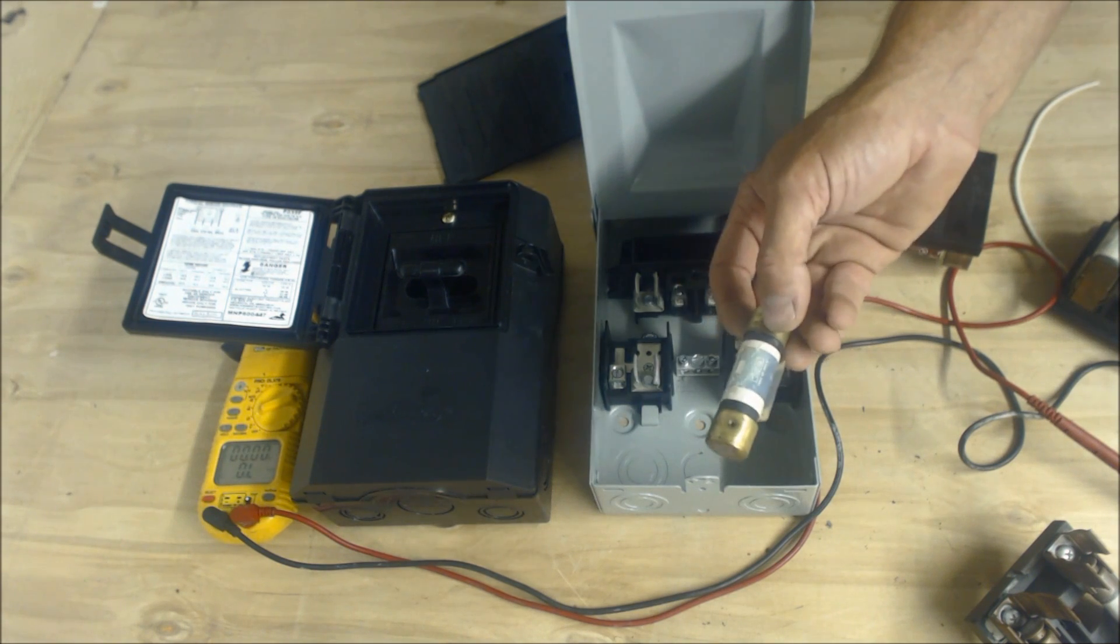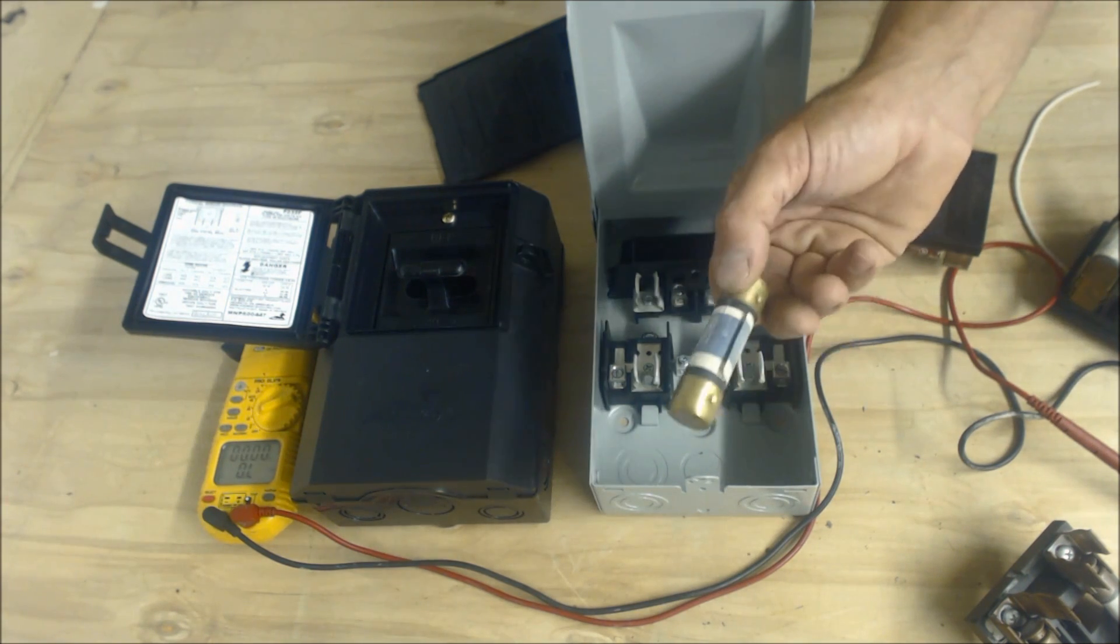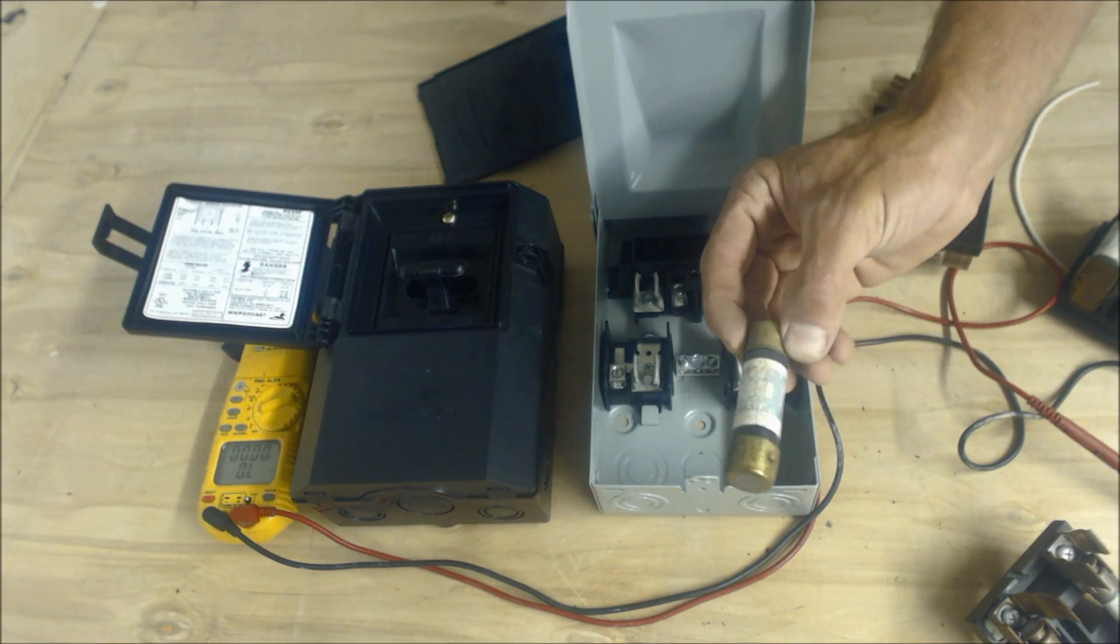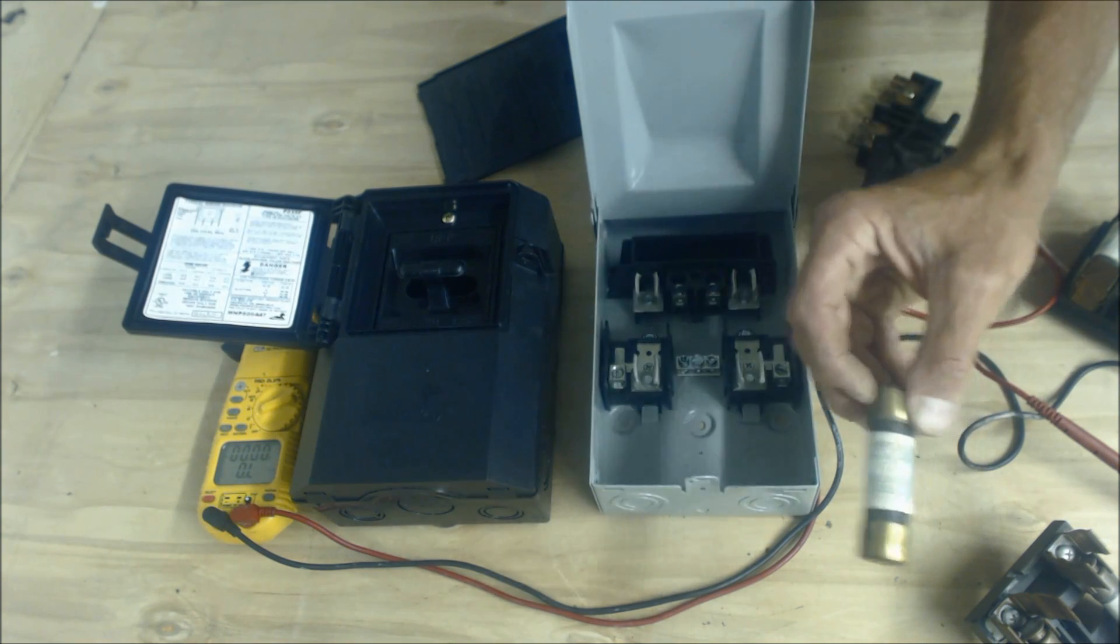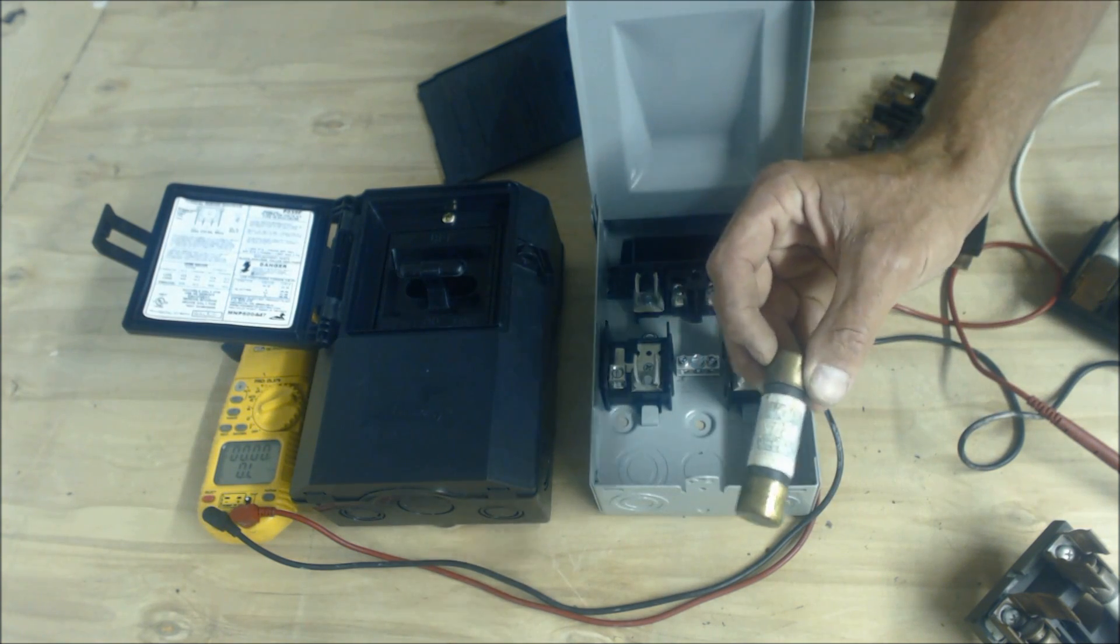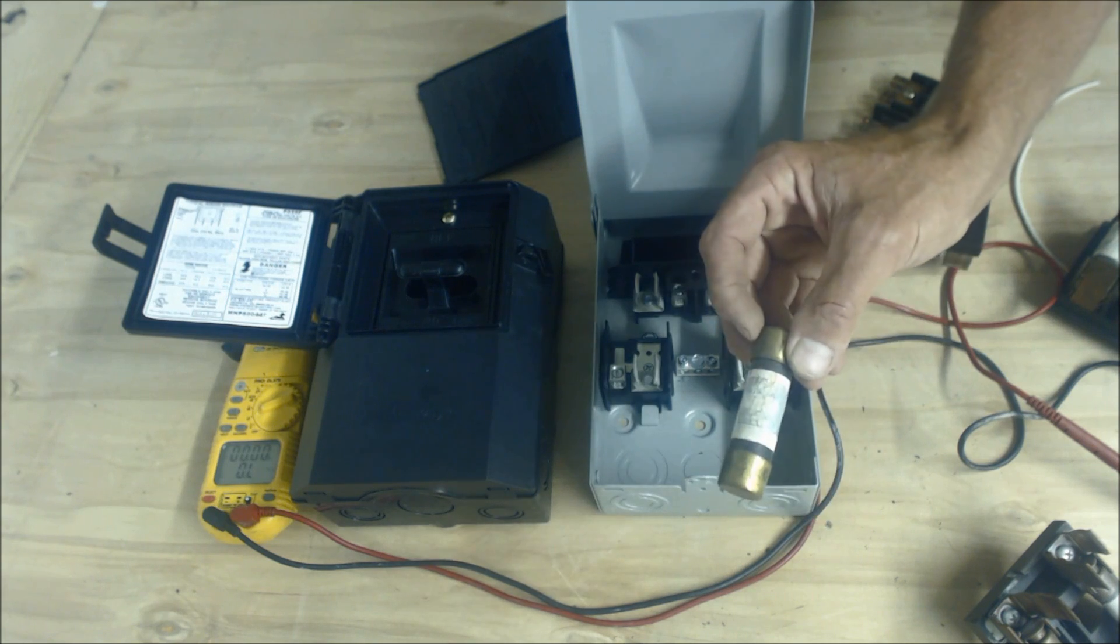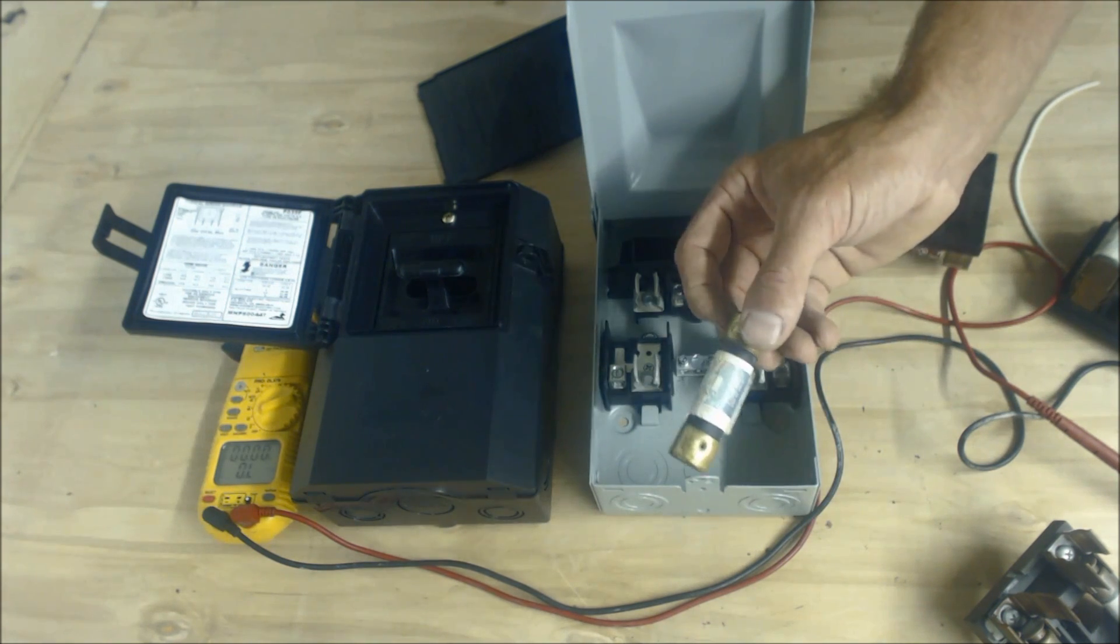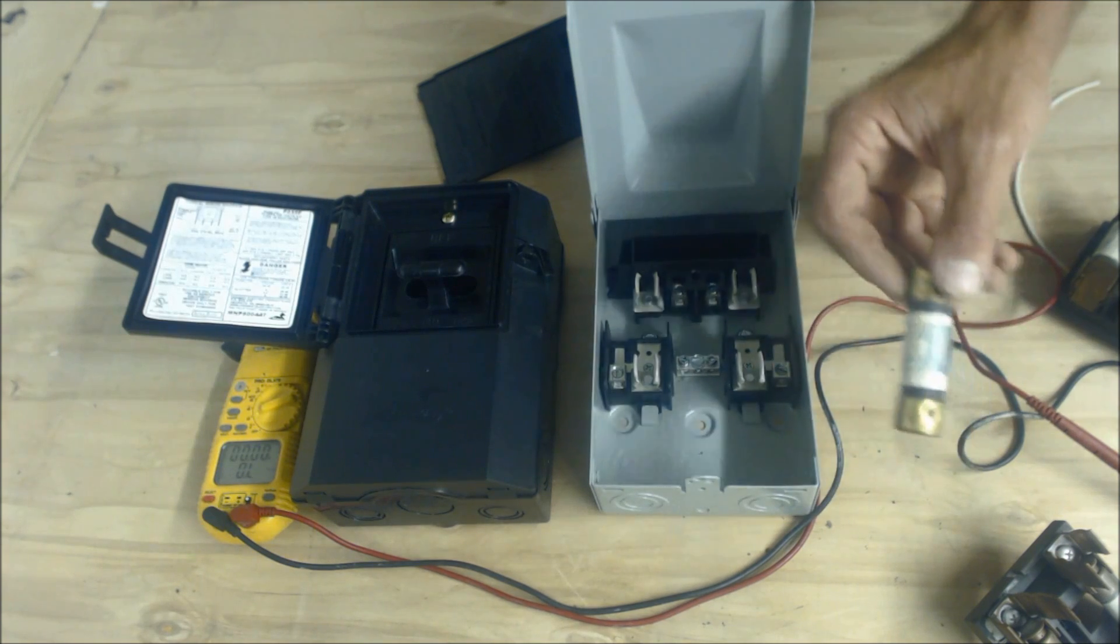These fuses are actually rated to handle that 100 amps of inrush current for the outdoor units. So for instance, an outdoor unit that runs 6 amps may run 100 amps for the first, say, quarter second or so when it turns on. If it takes in a steady current that's higher than what it's rated for, then it'll pop. There's no resetting them, then you just got to throw them away and put new ones in.